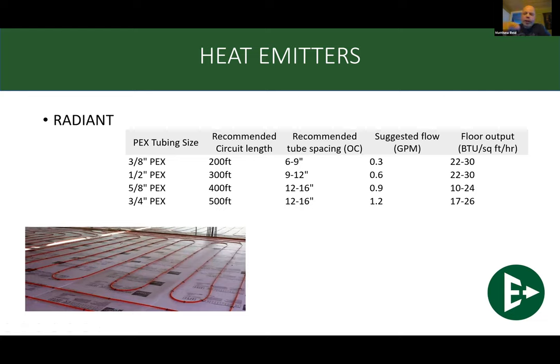Okay. Finally, we're going to talk about radiant. Now, radiant's a real tough one when it comes to checking the BTU output of a radiant floor system, because there are so many variables. But one thing I will tell you: the most common PEX size that goes into radiant in-floor heating is half inch PEX. A recommended circuit length is 300 feet. When you get longer than 300 feet, the head loss looks like a hockey stick. It goes up quite rapidly. We average space these out between 9 and 12 inches on center, and our usual flow rate is about 0.5 to 0.6 GPM per loop. With that math, we get between 22 and 30 BTUs per square foot of radiant heating.